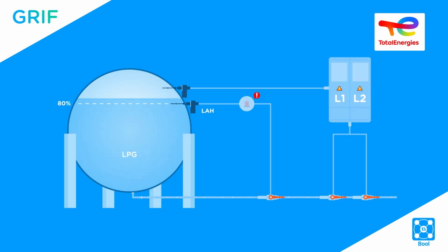If the first barrier is down and the gas level is upper than 90%, a safety instrumented loop is implemented. The safety system is one level sensor, LSHH, connected to the control unit, and the final action is to close one of the two SDV.